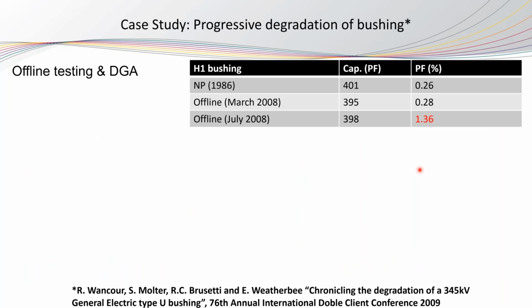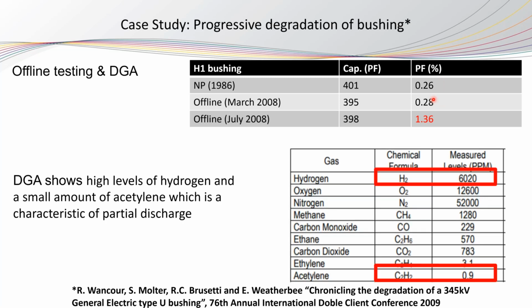So the decision was to take the transformer out of service and do offline testing. They found out that the power factor was 1.36, and it was quite high compared to the previous test session and to the nameplate value. So they did another diagnosis. They took an oil sample from the bushing, and they found a very high value for the hydrogen, 6020, and a low value of the acetylene, around 0.9 ppm. In bushings, this is an indication of partial discharge.